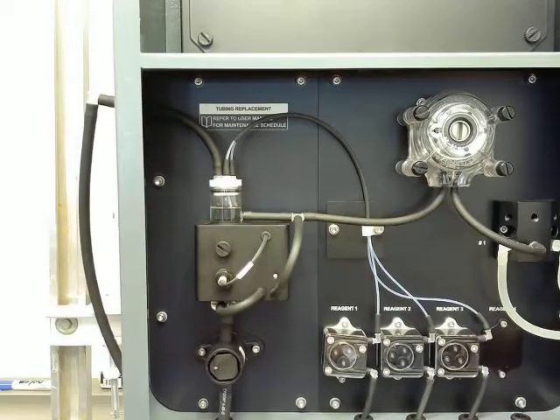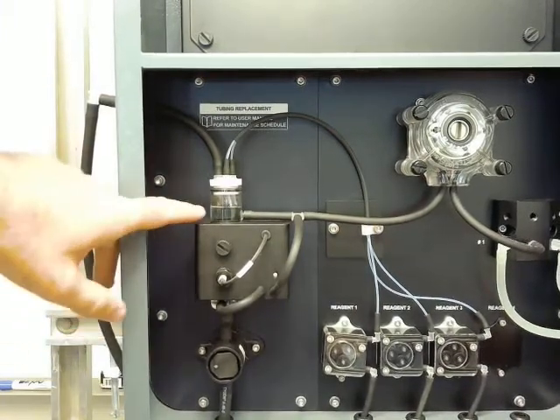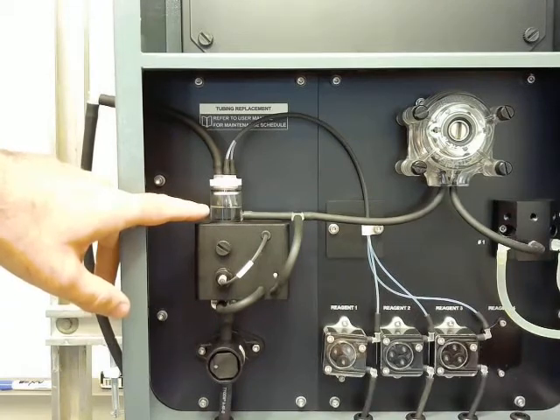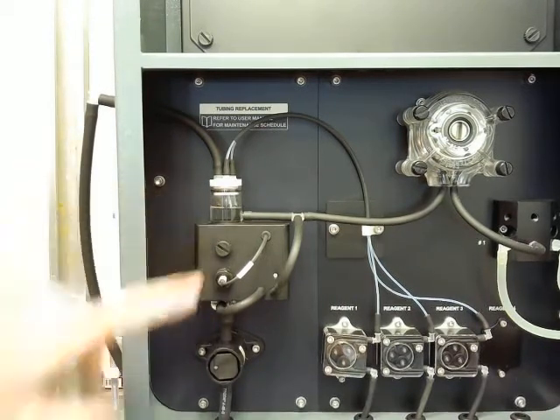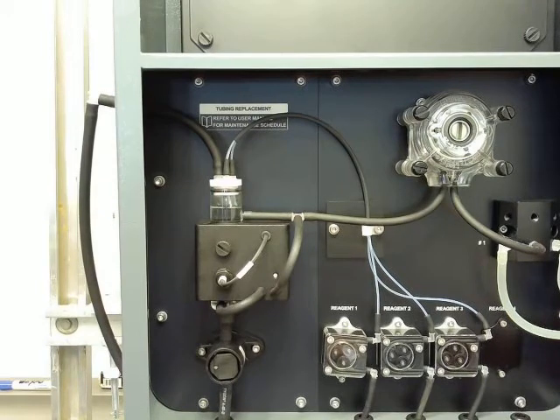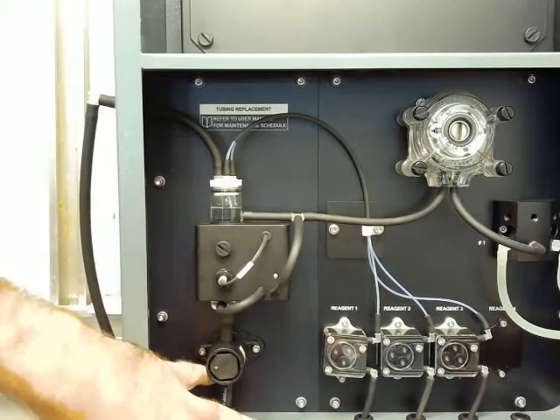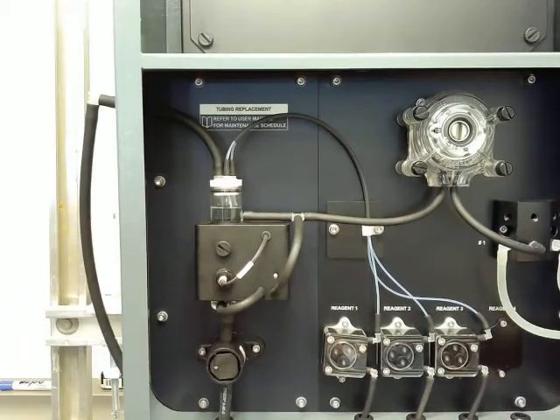Once that flow cell fills up, that's where we can get a good indication that we did our drain tubing correctly as well. If we just watch the level in this flow cell for a few seconds and that level stays constant, most likely we did a good job. If we see that the level in that flow cell is slowly draining even with the valve not activated, it just might mean we have a little twist in the tubing. It just needs to make a better connection, better mating with that pinch mechanism. So we can usually just wiggle that tubing in place a little bit more and it usually straightens out.